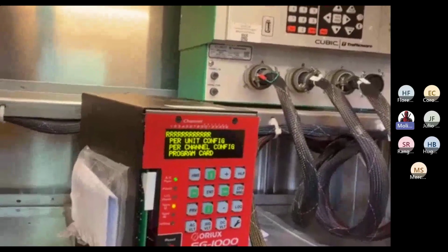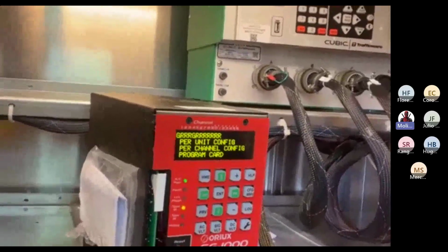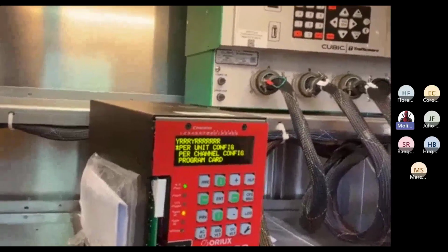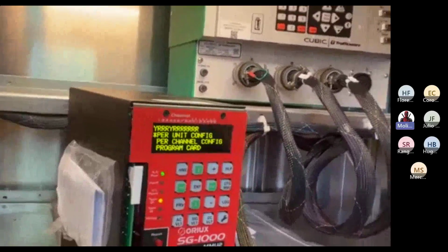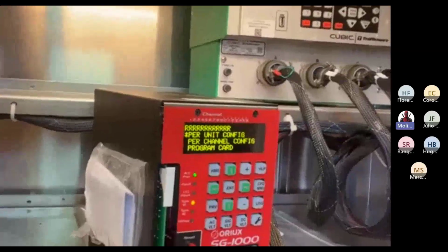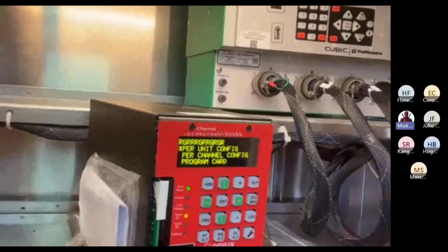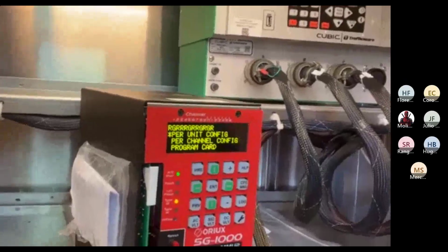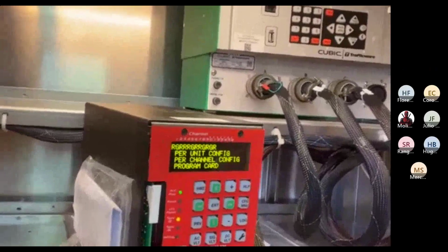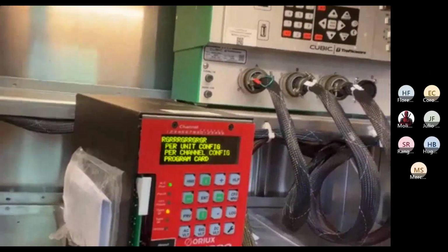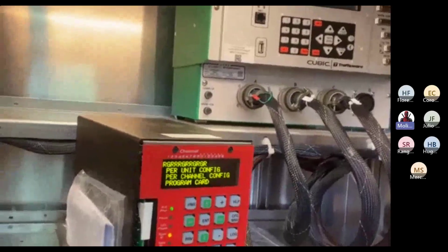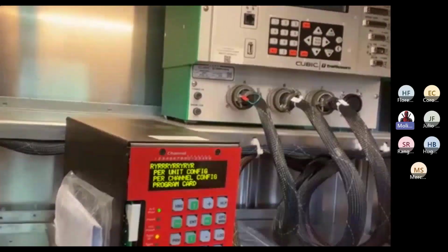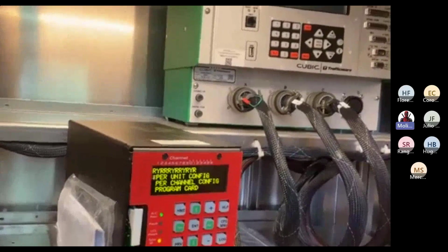So that's the only thing that goes away: the fault information, the status of the voltage, after you reset it. Remember when I showed you on the voltage screens where it was reading the voltage outputs on everything in real time? It's that snapshot of what happened at the moment of fault. As soon as you start it back up again, that clears out, and the values in those fields go back to the current reading. That's why it clears it out.